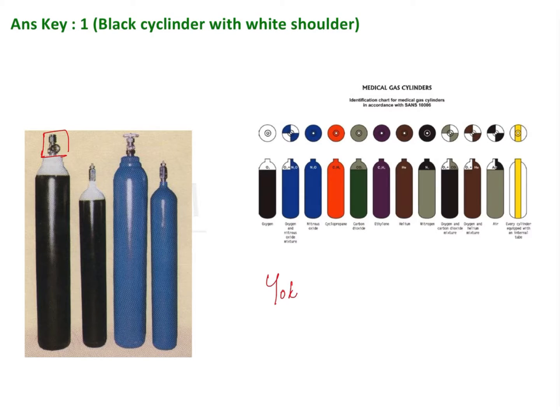The cylinder has a few important parts. There is the valve, through which the yoke of the ventilator is connected so that gas can pass through into the ventilator and the patient can inhale it. This part is called the shoulder, and the vertical part is called the body. Depending upon the color of the body as well as the shoulder, anesthetic and medical gases have been color coded in a specific way. Oxygen is a black cylinder, meaning the body is black and the shoulder is white.